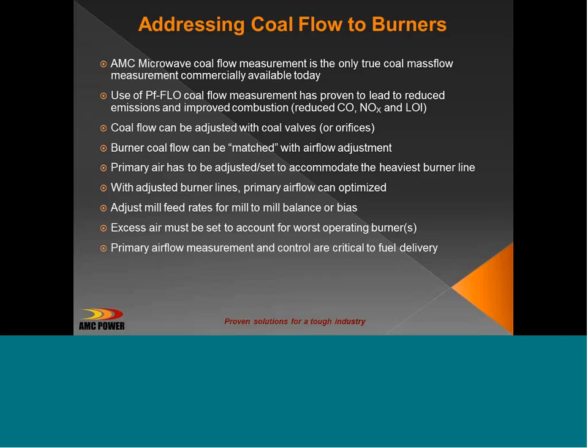Primary airflow also has to be adjusted to accommodate the heaviest burner. If an operator has problems with potential pluggage, he's going to increase his primary air. Meanwhile, the other burners, which may be light, you're going to be blowing your coal right through your flame. You're going to have elevated superheat and reheat temperatures, high unburned carbon, and so on.